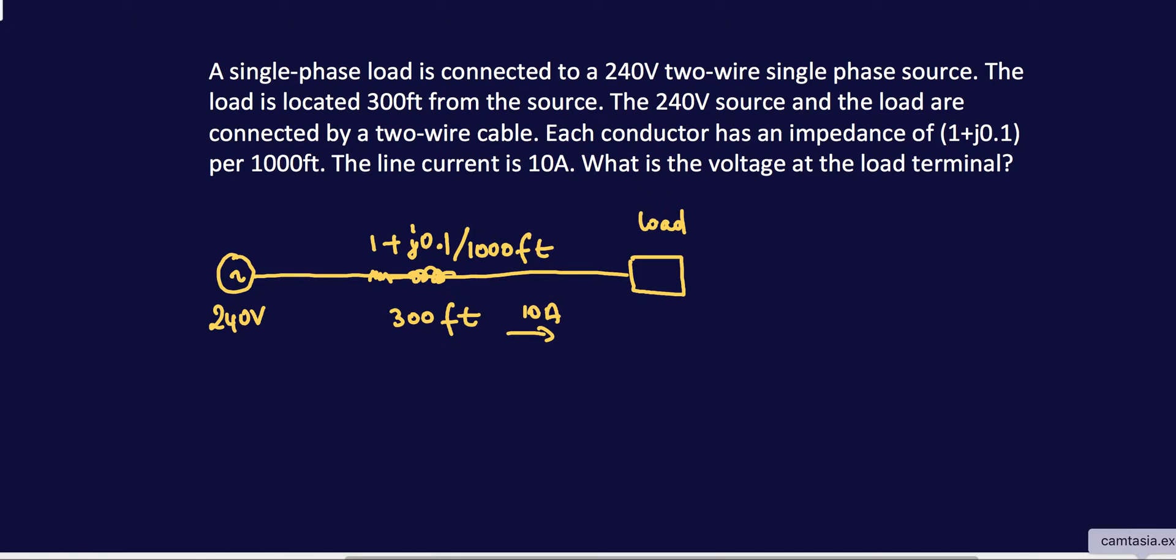Hello and welcome back to another video. We have an example here of a single-phase voltage drop problem. We are given a load, a single-phase load, connected to a source of 240V at a distance of 300 feet from the source. Each conductor has an impedance of 1+j0.1Ω per thousand feet. Given a line current of 10A, we are asked to find the voltage at the load terminal.